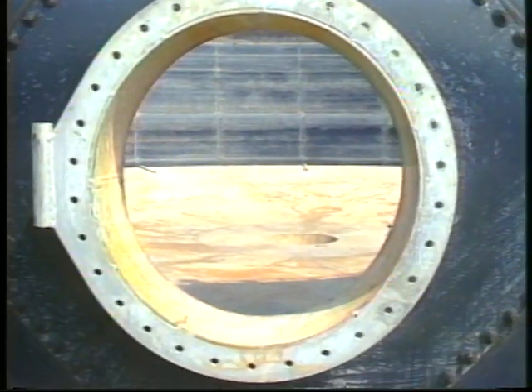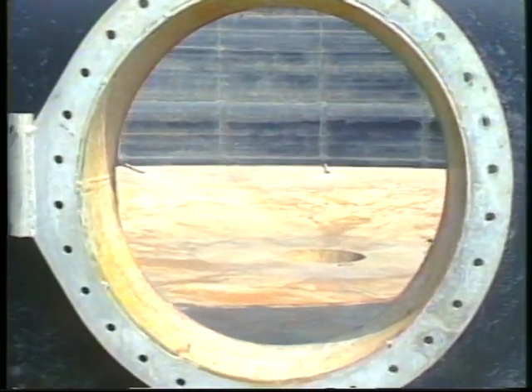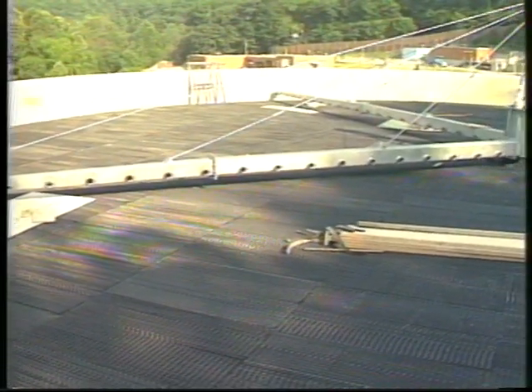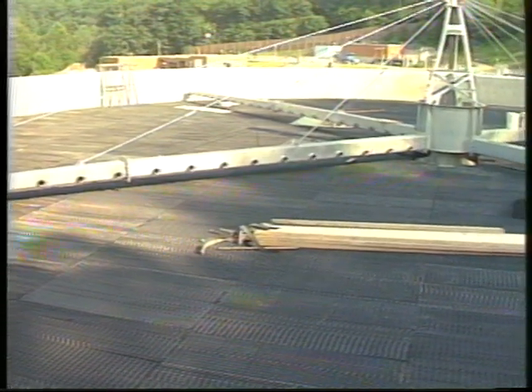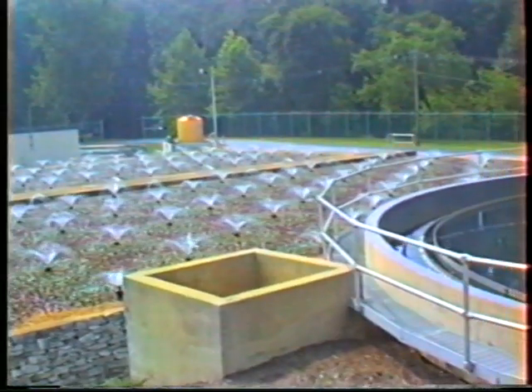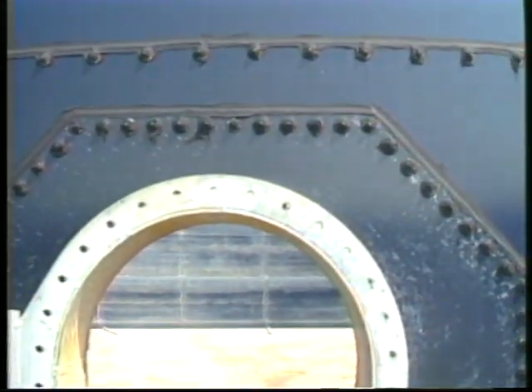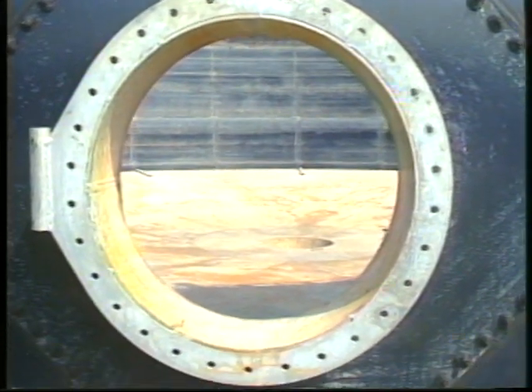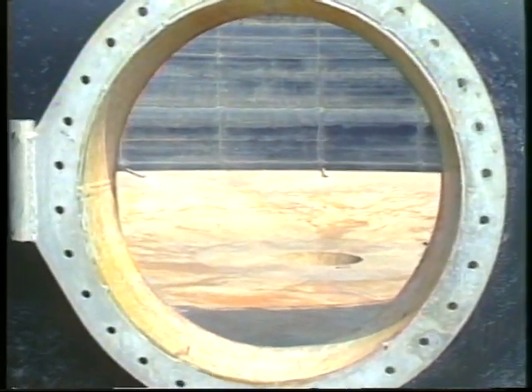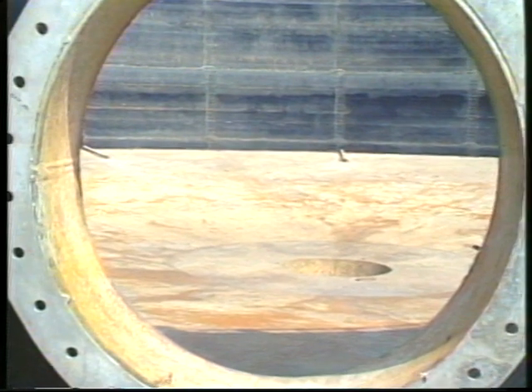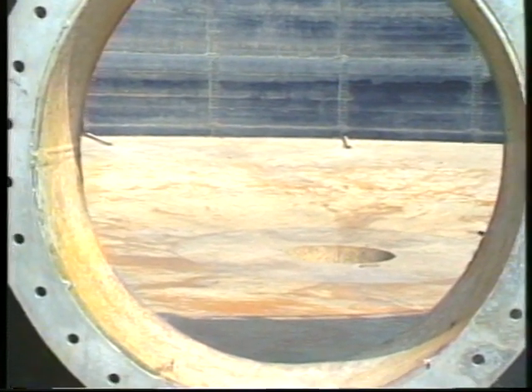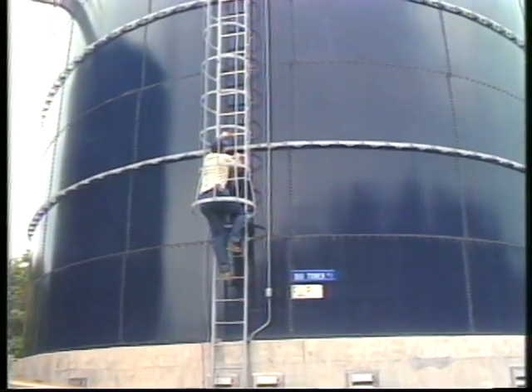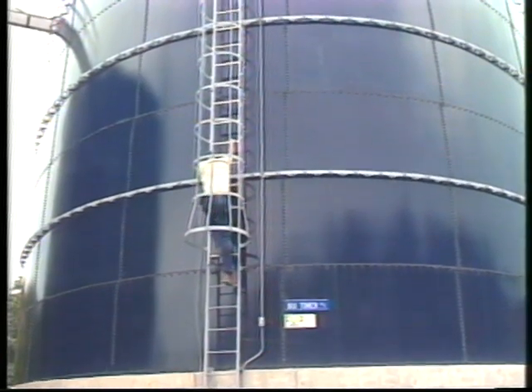First, let's take a look at the retaining structure. The structure houses all of the other major components of the trickling filter. The structure may be either round or square and could be anywhere from 4 feet to 50 feet tall, depending upon the design of the filter. Materials commonly used for the construction of trickling filter structures include concrete and a special ceramic coated steel. The taller filters usually have ladders for easy access.